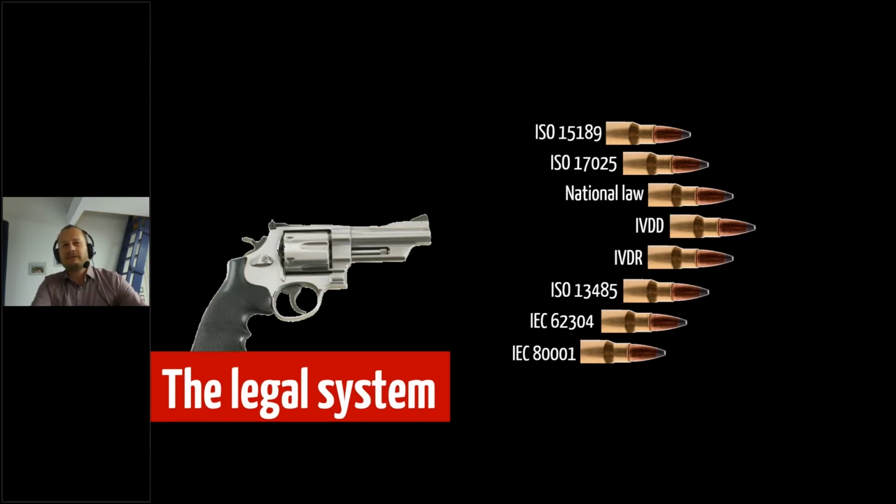These include standards like ISO 15189 for medical laboratory quality management systems, ISO 17025 for laboratories without a medical context, national laws, the in vitro diagnostic medical device directive, which is the current legislation, and the IVDR, which is the future regulation. Then we have standards for manufacturing of medical devices, and standards for software life cycle and IT security, which are applicable.